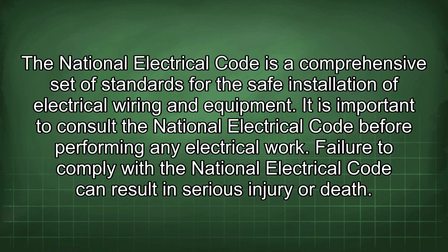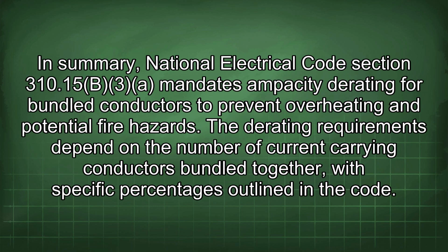The National Electrical Code is a comprehensive set of standards for the safe installation of electrical wiring and equipment. It is important to consult the National Electrical Code before performing any electrical work. Failure to comply with the National Electrical Code can result in serious injury or death. In summary, National Electrical Code Section 310.15(B)(3) mandates ampacity derating for bundled conductors to prevent overheating and potential fire hazards.